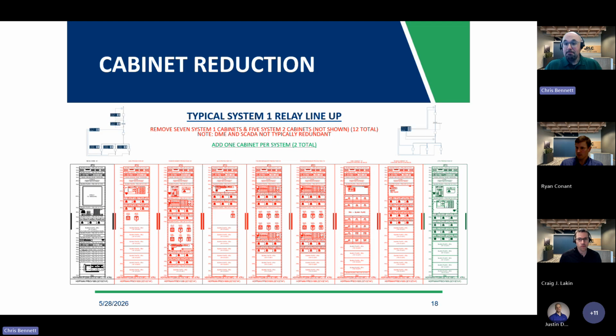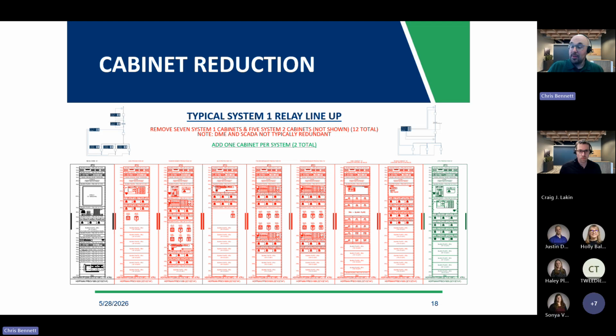So a visual graphic of what we are talking about for CPC: you see in red a traditional design, for something that Craig had mentioned before, with a single incoming line, a transformer, and 3 feeders. We can replace seven of those racks with one centralized protection rack per system. Depending on your requirements for system separation and redundancy, you may be able to get away with just the one. Typically, 2 is recommended for redundancy.